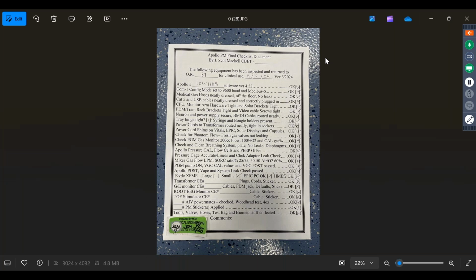So half our machines, you know, you can just press the magic keys and service mode pops up. If you buy these machines, definitely order them with the service mode unlocked, because if your laptop, if your subscription to Draeger Service Connect expires and you don't know it, and you're in the OR at like 7 o'clock setting up to do a machine PM, and then you go to use your service software and it's 9 o'clock, you're screwed. You know, Draeger tech support ain't gonna help you at that point, and you can't get into service mode. So going on with the PM checklist.